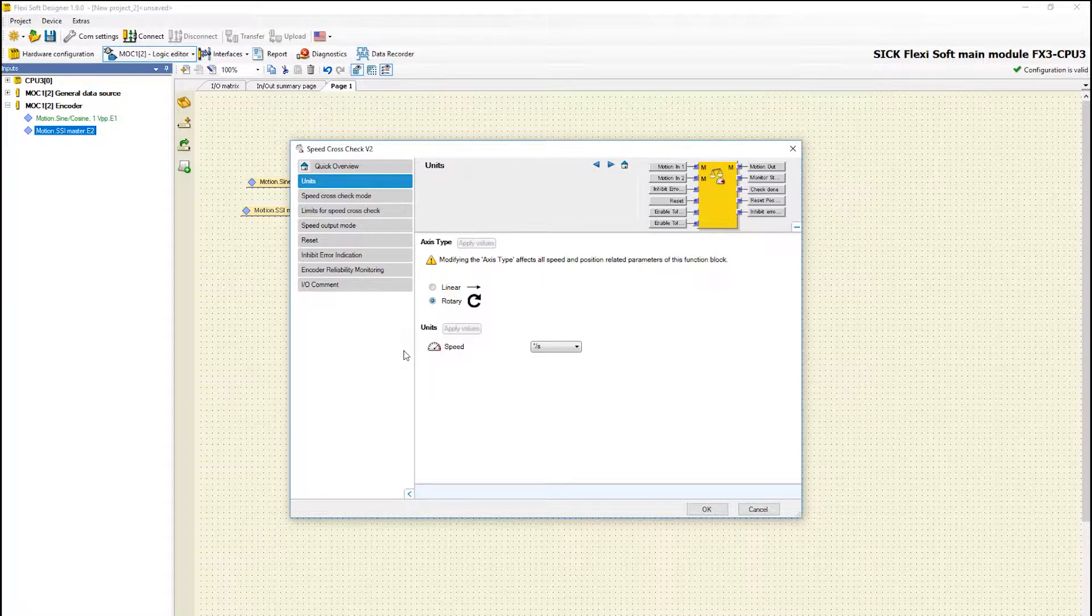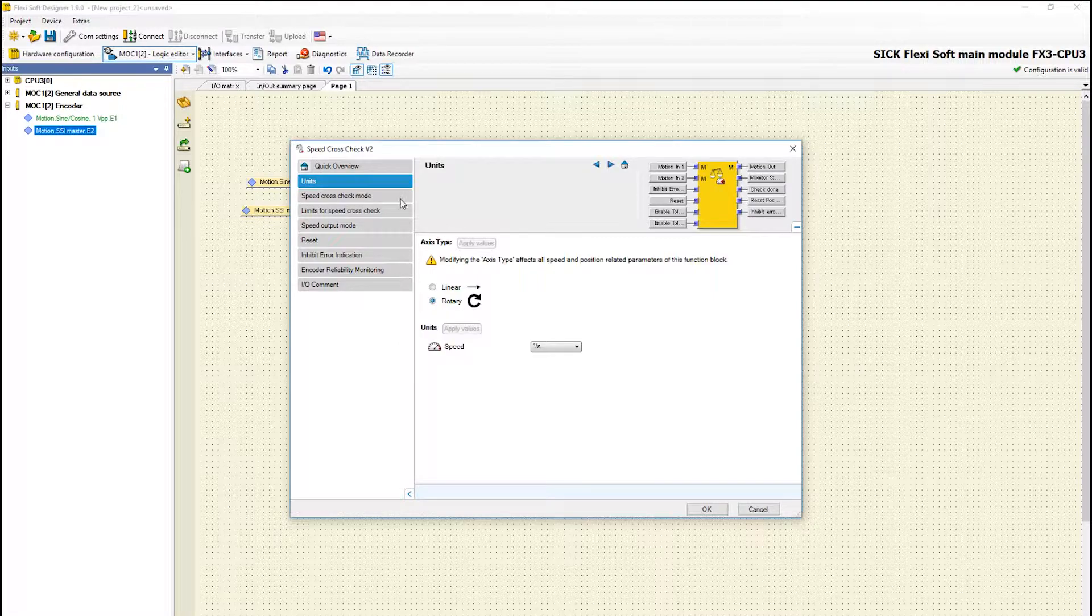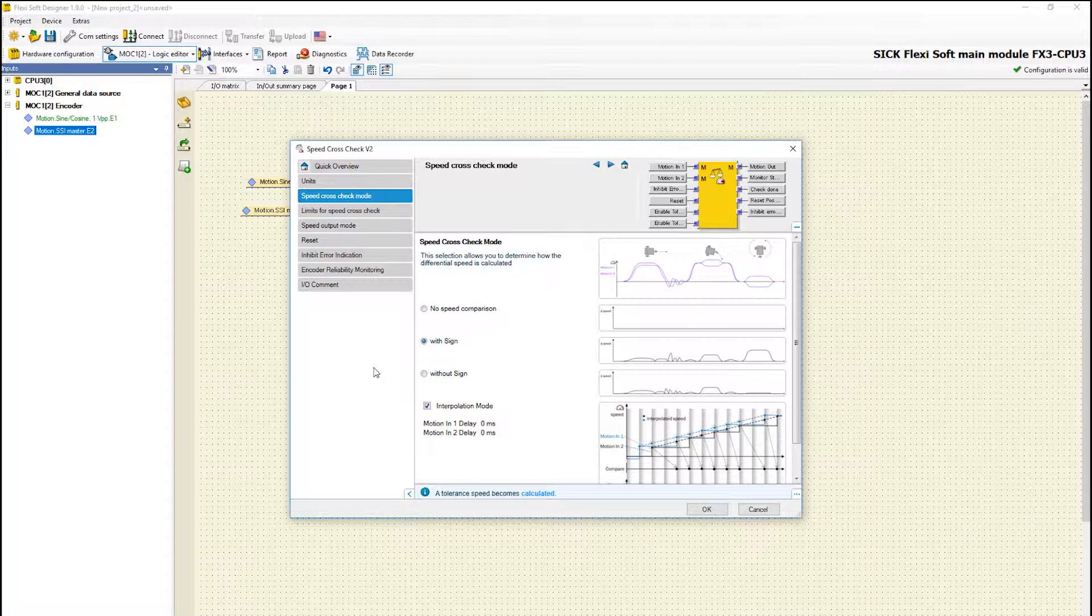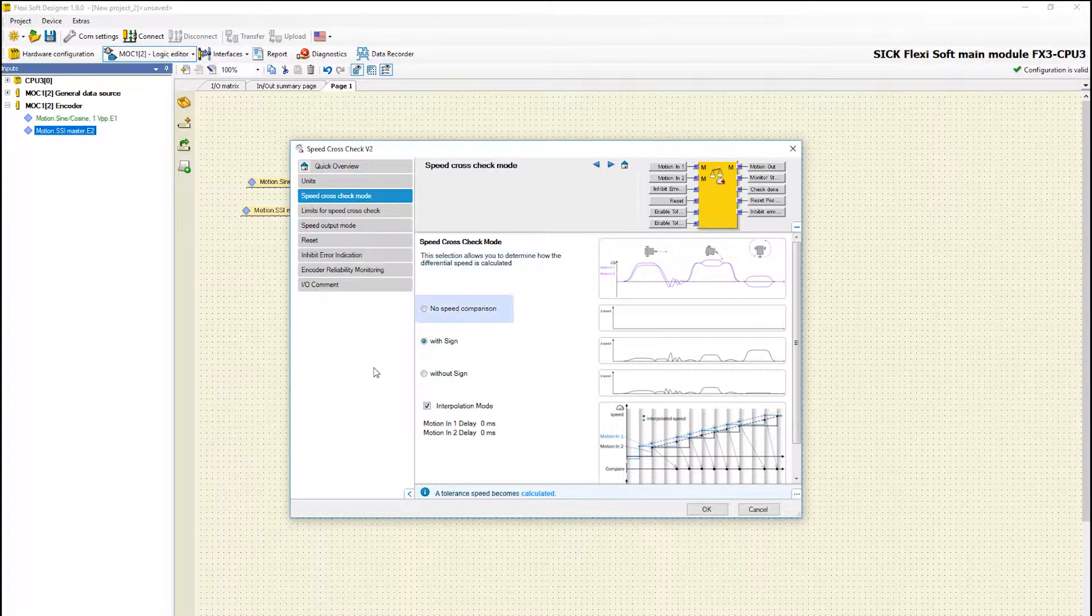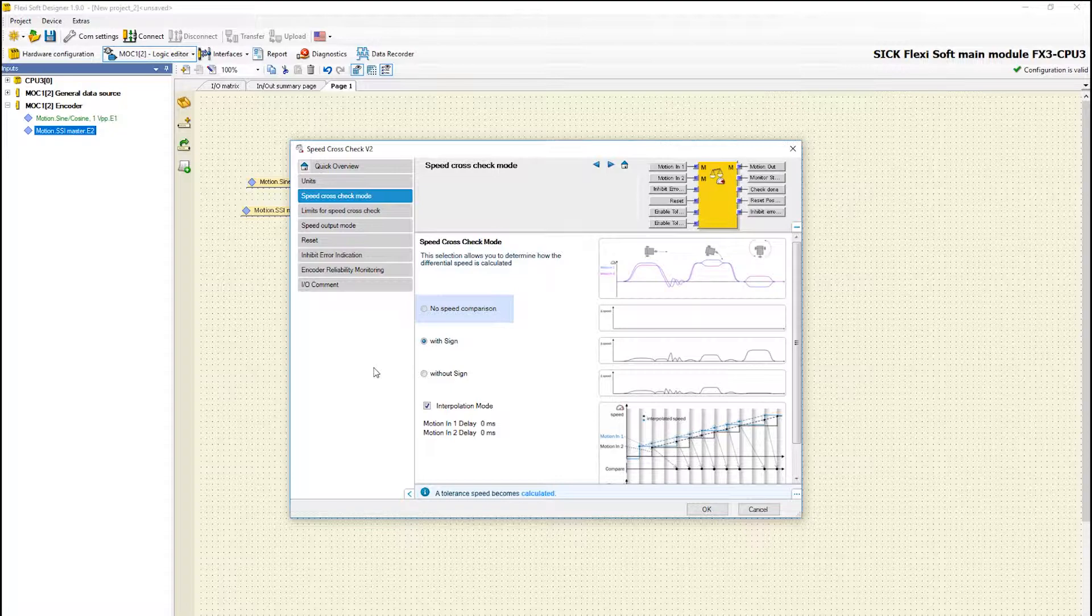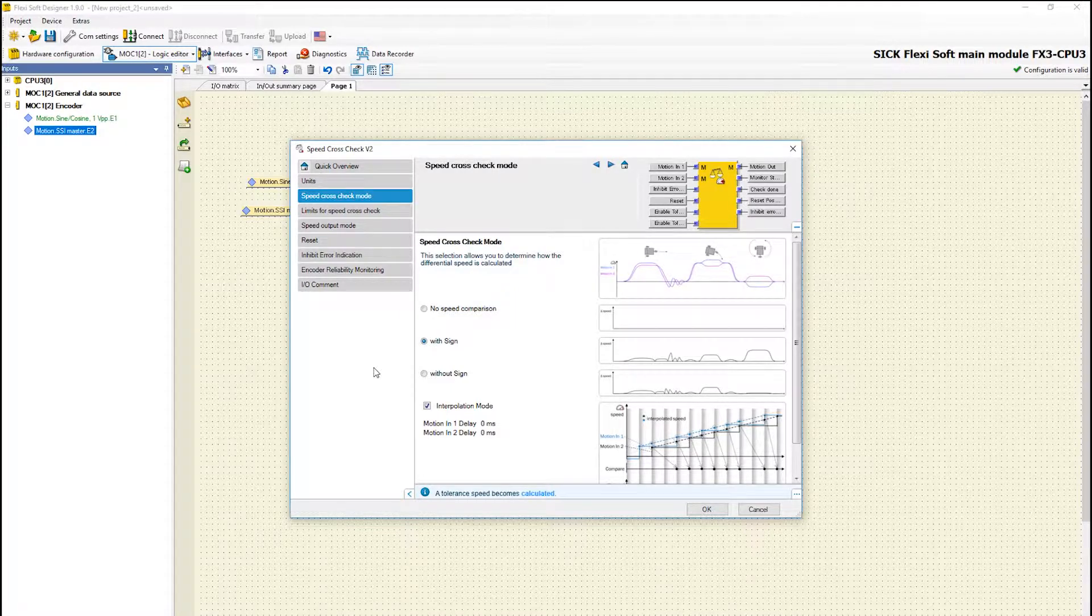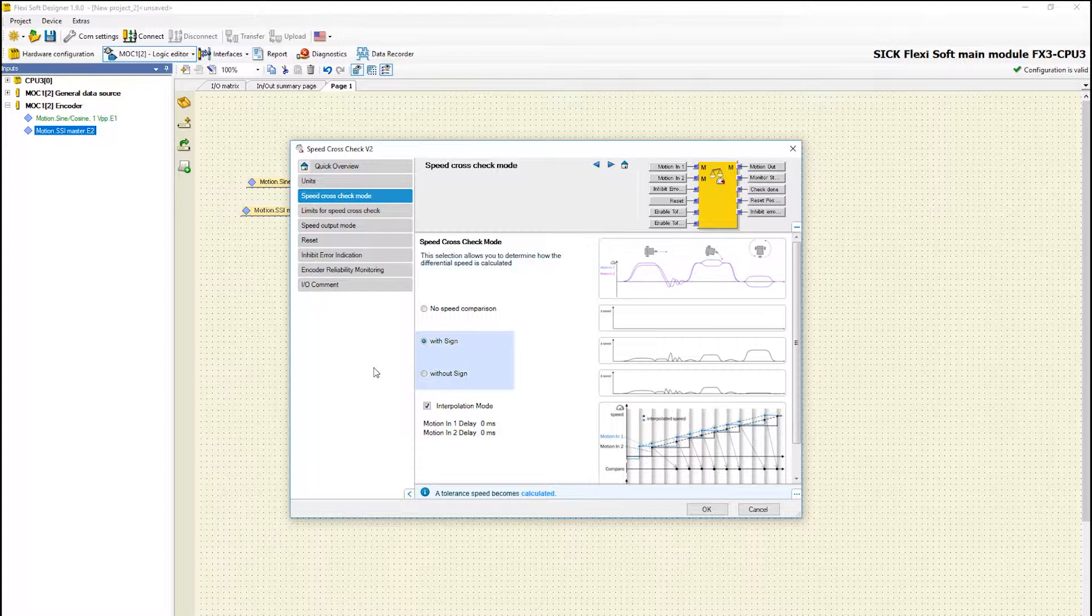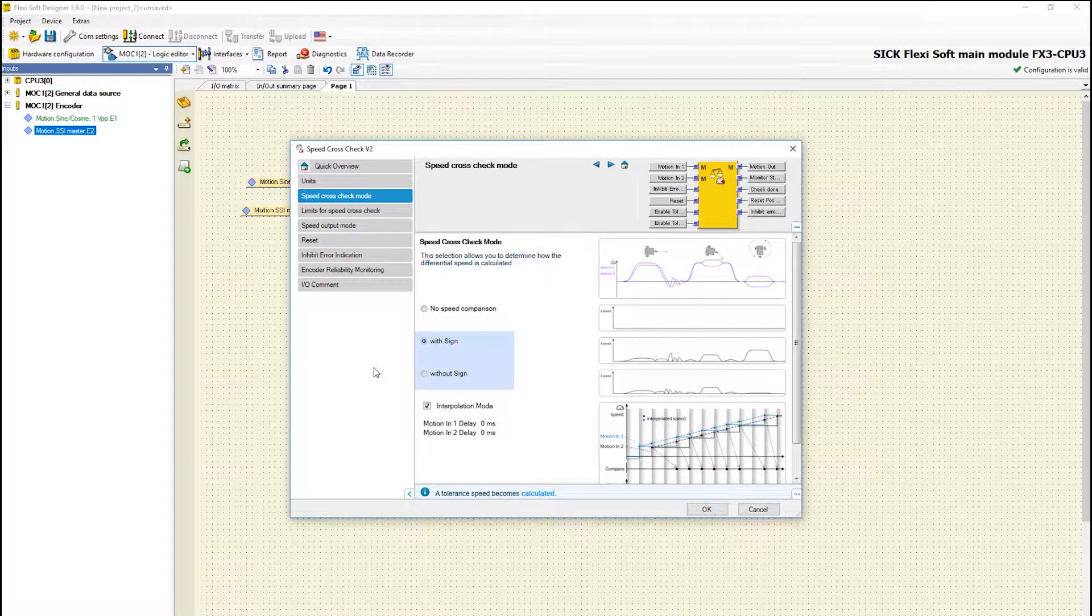In the next tab speed cross check mode you are able to determine how the speed values are compared. If the parameter no speed comparison is activated the speed values will not be cross checked. If the speed cross check mode is activated the speed cross check will be performed. Depending on the set mode the speed difference is determined with or without sign.